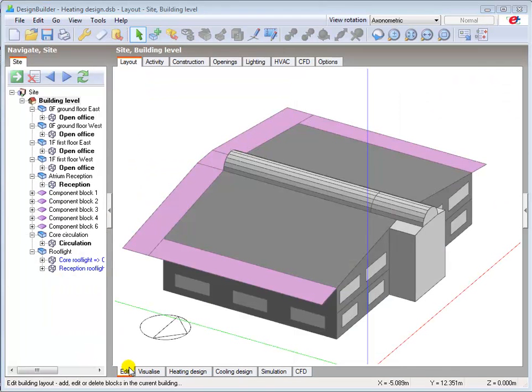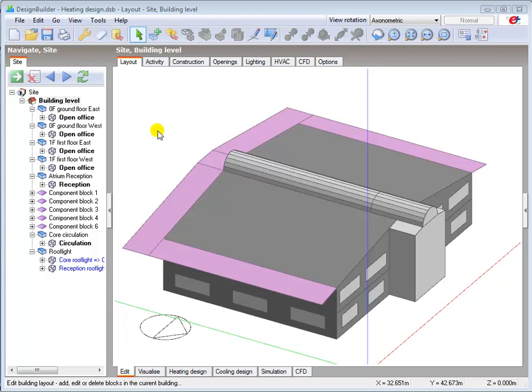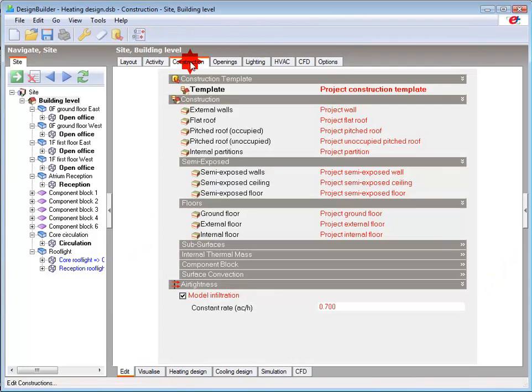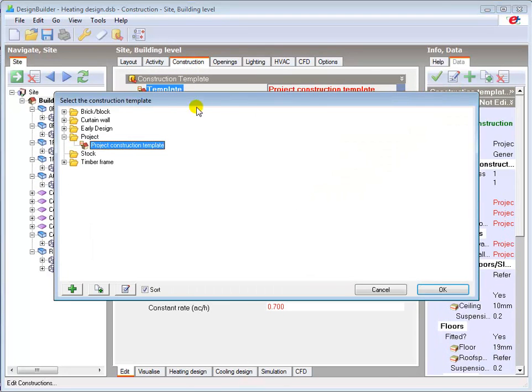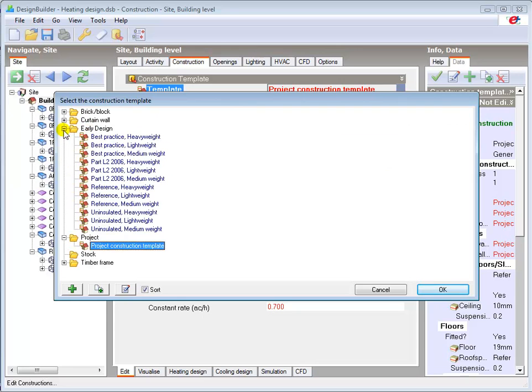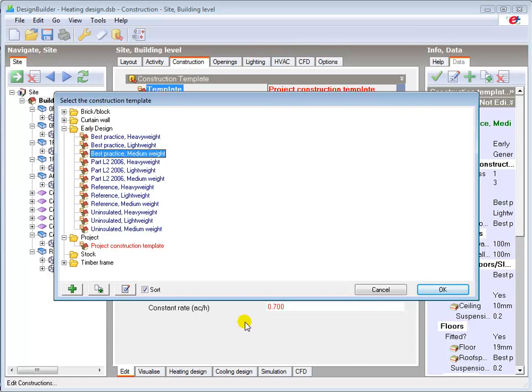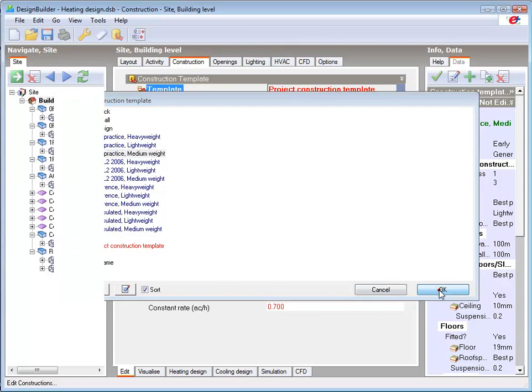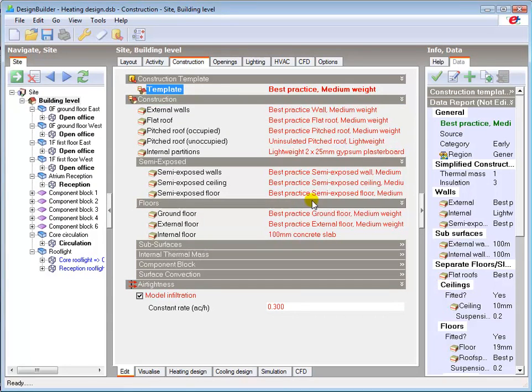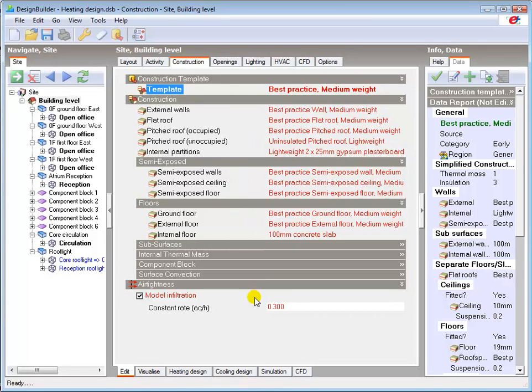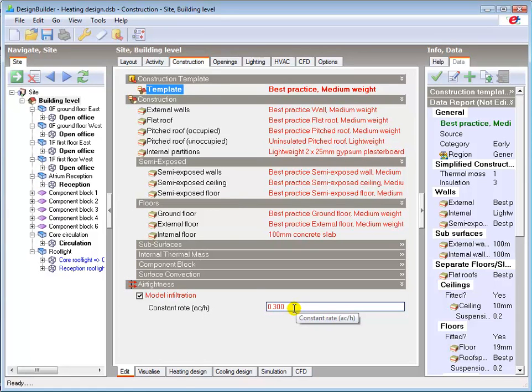I will now show you how quickly we can make some fairly significant changes and quantify the benefits in terms of improved thermal performance. Going back to the construction tab I will load the best practice medium weight template. This will load higher performance constructions such as the roof and walls. And immediately you can see that the default infiltration rate has reduced from 0.7 to 0.3 air changes per hour.